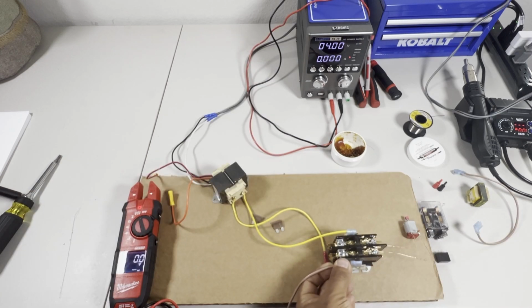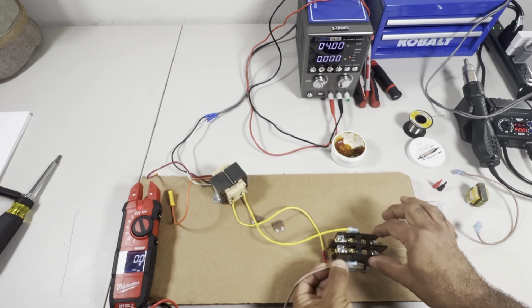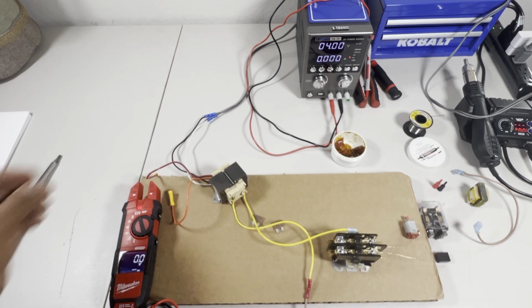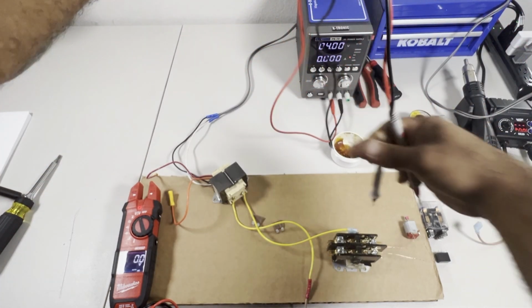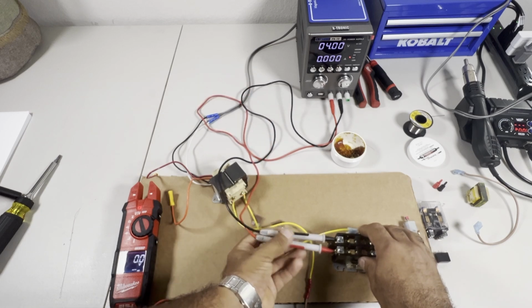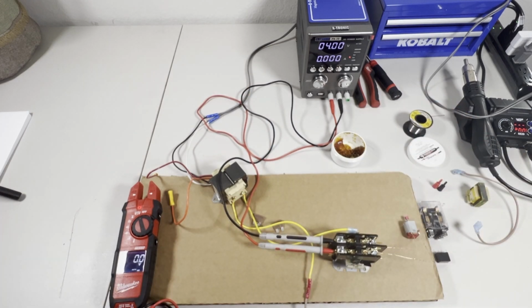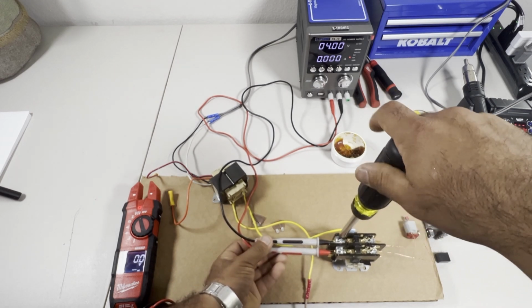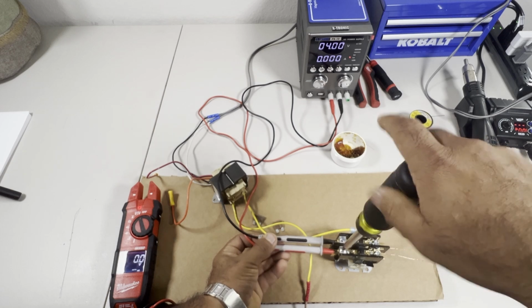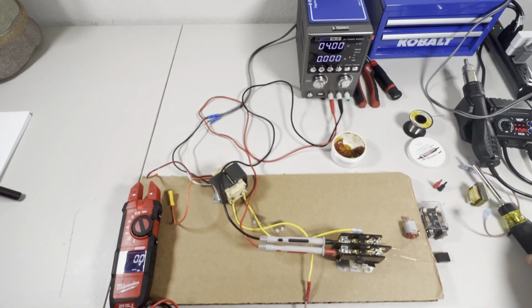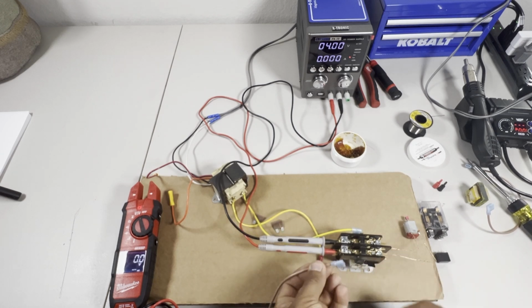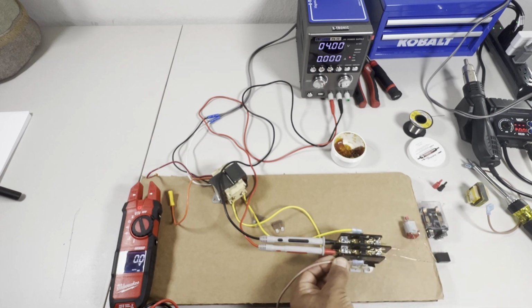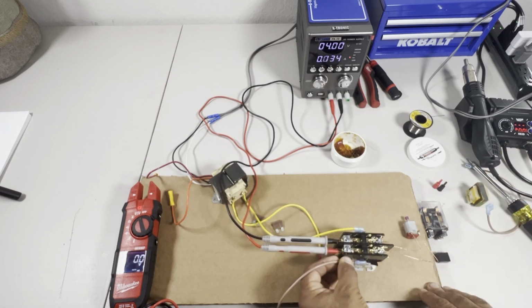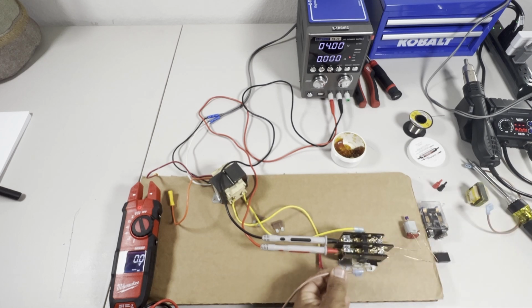I want you to see what happened to this coil. Did you see that? This is the power that is coming from the main breaker. They go to the bottom of the contactor. They just wait until there is a signal wire coming in from your controls, which is the thermostat, control board, whatever the case might be. And here you go. Your compressor, your motor, whatever it is, is going to be running and running and running until the thermostat is satisfied and it will stop.